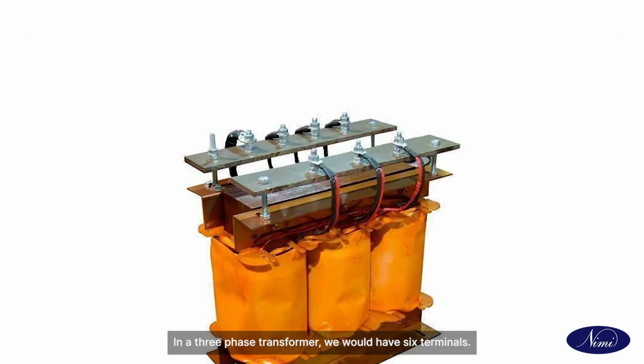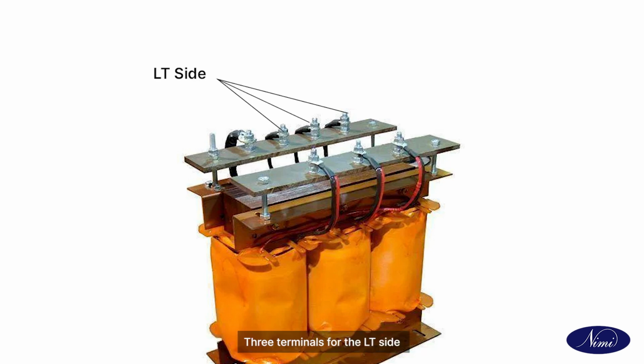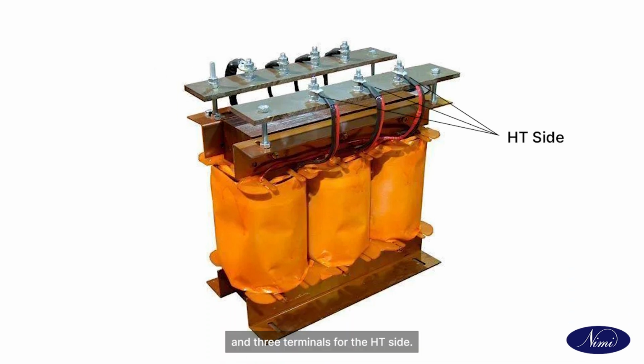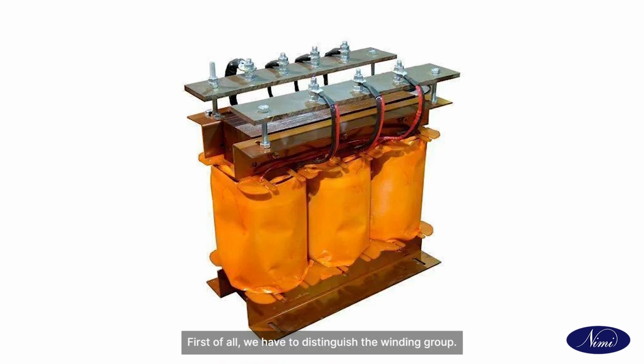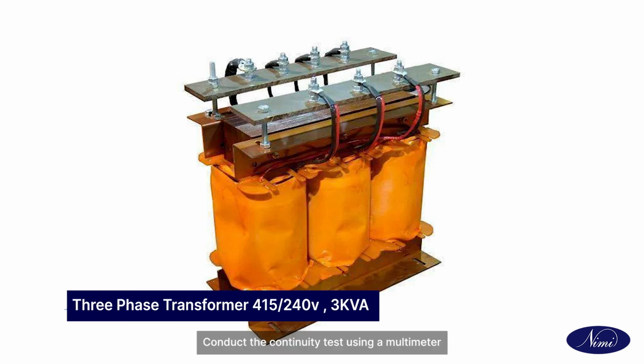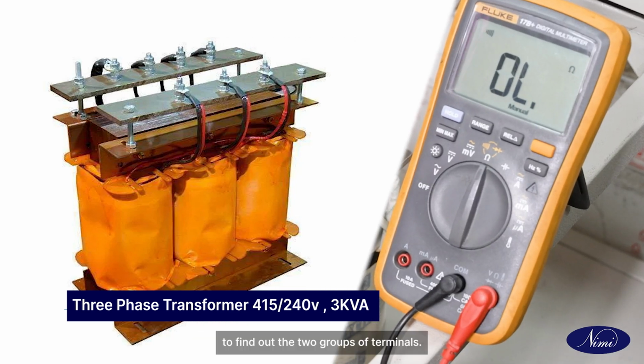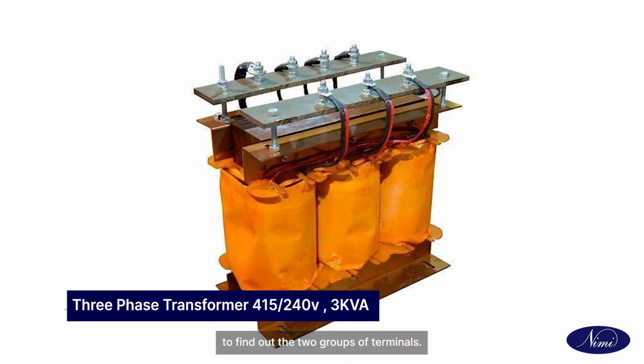In a three-phase transformer, we would have 6 terminals: 3 terminals for the LT side and 3 terminals for the HT side. First of all, we have to distinguish the winding group. So, let us conduct a continuity test between the winding terminals. Conduct the continuity test using a multimeter to find out the 2 groups of terminals.